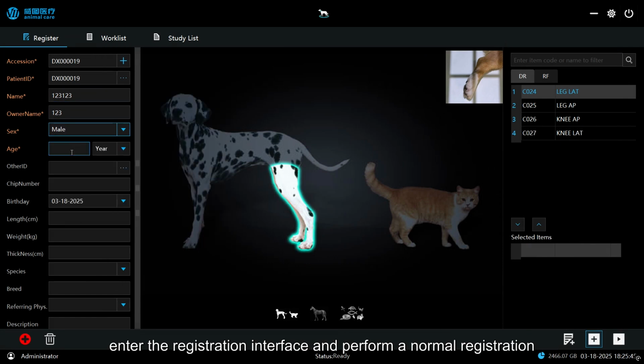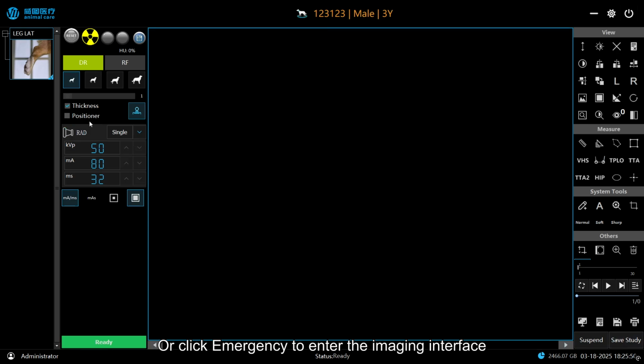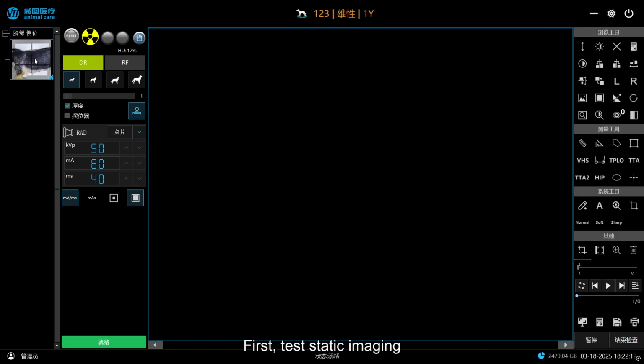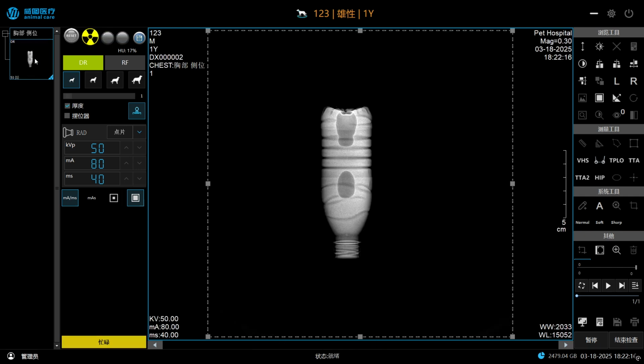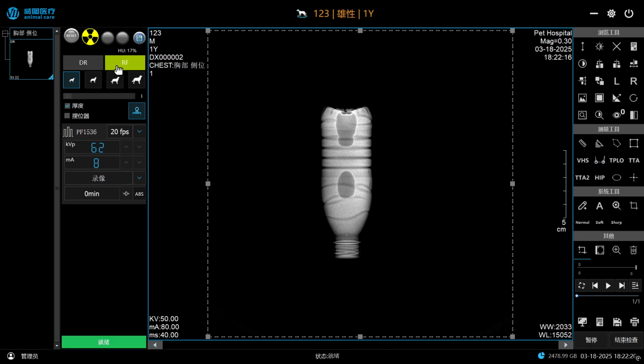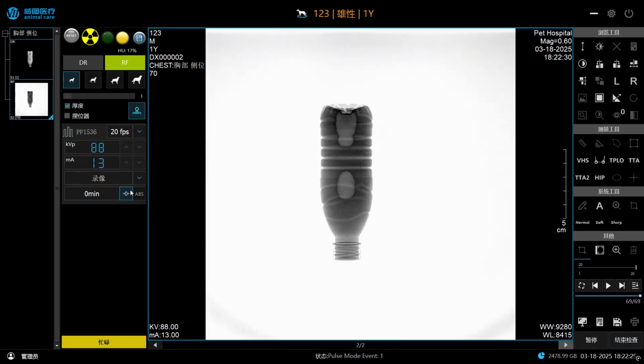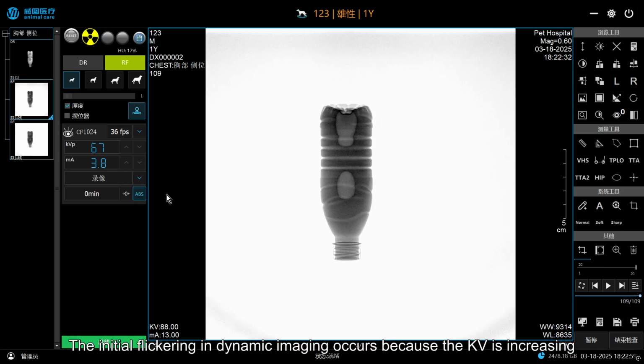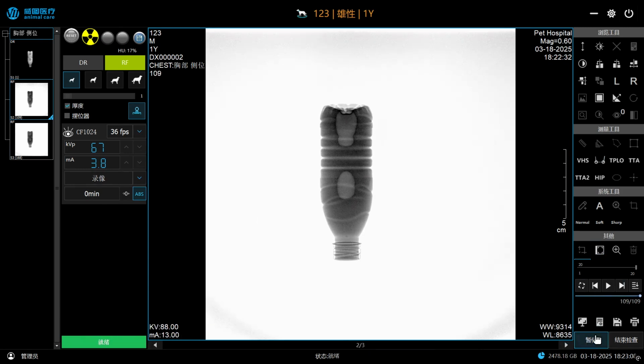20. Test software. After completing the settings, enter the registration interface and perform a normal registration. Or click Emergency to enter the imaging interface. First, test static imaging. Then test dynamic imaging. The initial flickering in dynamic imaging occurs because the KV is increasing. Once stabilized, you can view the images normally. After completing all tests, proceed to the aging test.